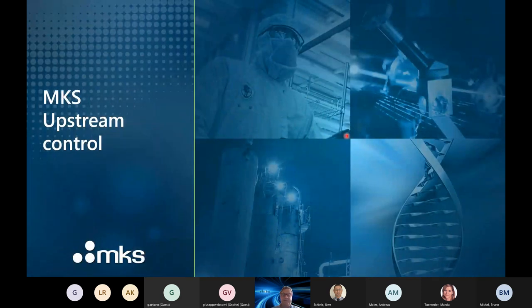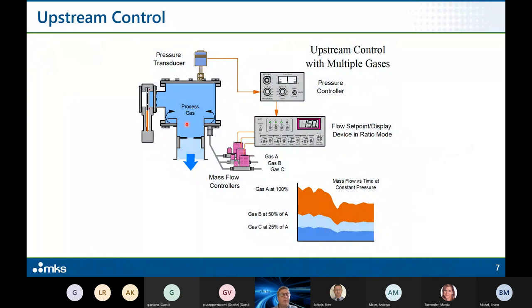We start with upstream control. Here's a simple schematic of a process chamber: the blue represents the process gas, the arrow shows the direction toward the pump, and at the top is the pressure transducer providing the pressure signal to a pressure controller. The controller compares the pressure signal with the set point and generates a control signal to a valve or mass flow controller, adjusting the flow to increase or decrease it as required to reach the right pressure.